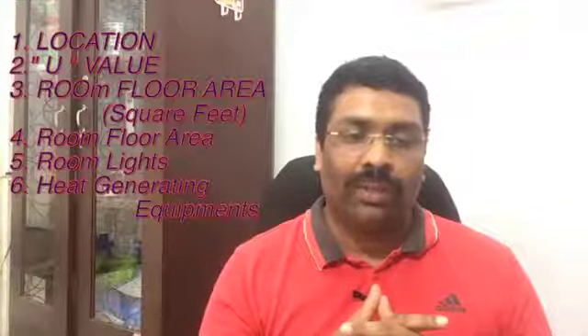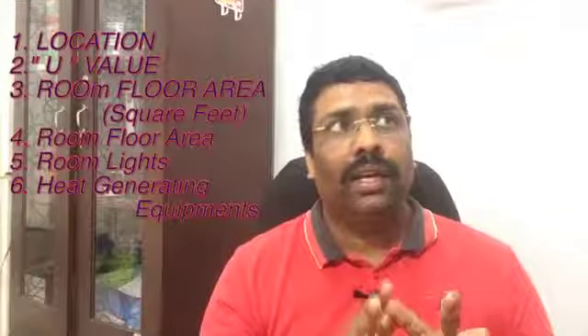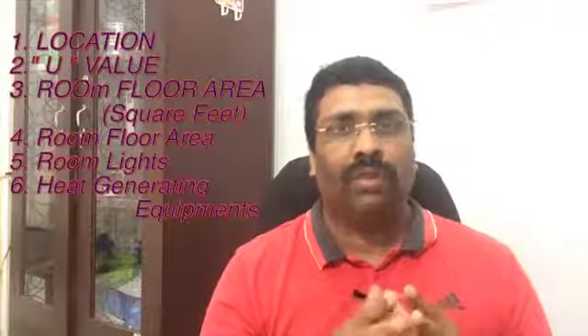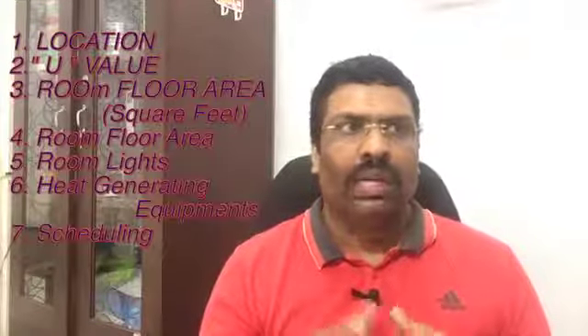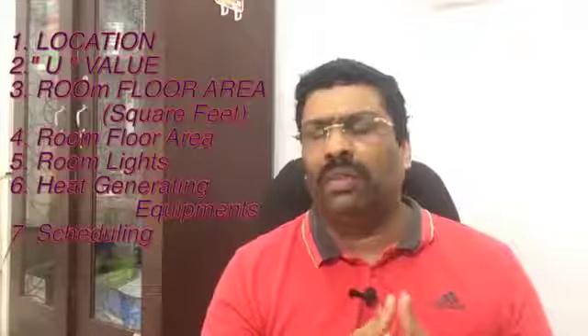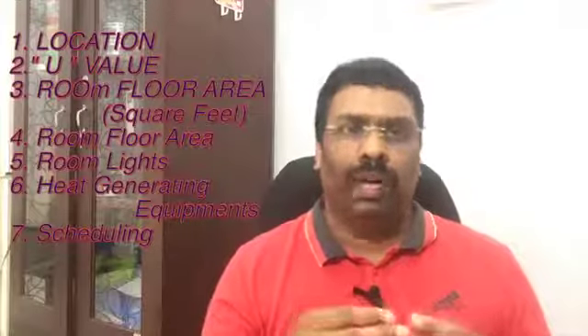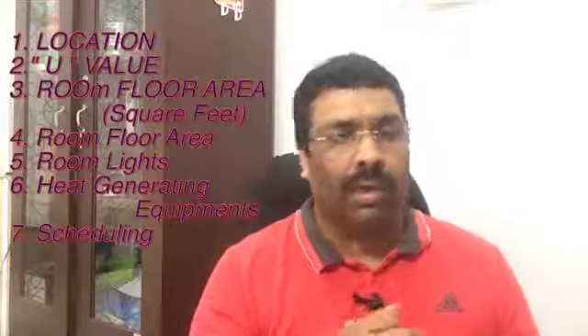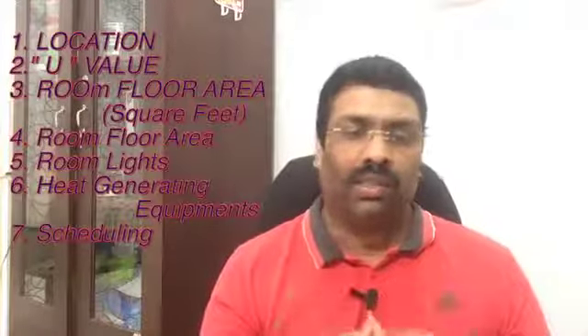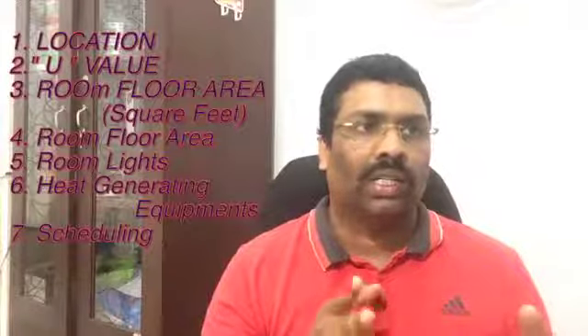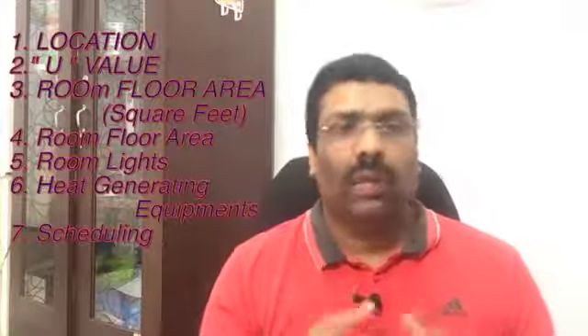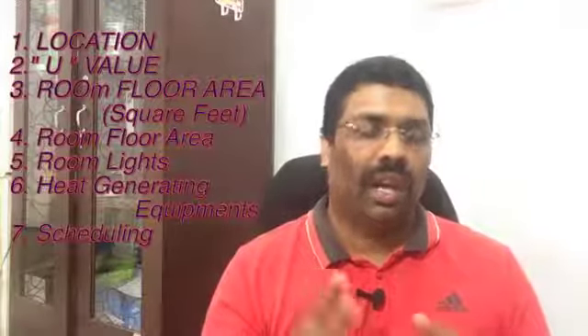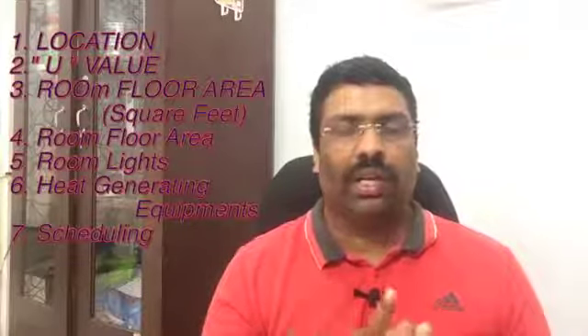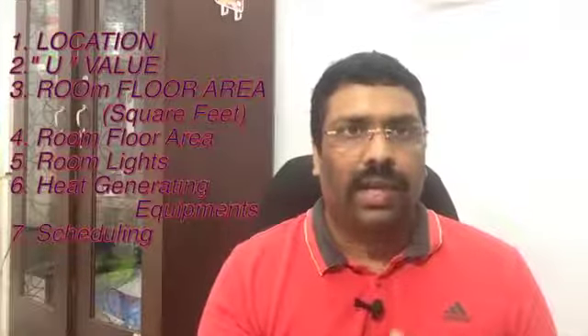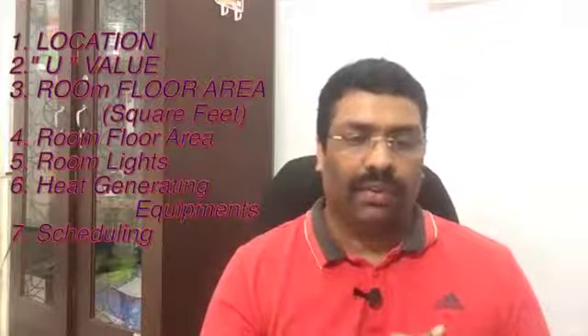The seventh point is there's an advantage in the HAP software: we can give intervals for lighting or equipment working hours. Normally in regular cases nobody does that, but for big commercial buildings we need to consider lighting and equipment intervals. Some equipment works only in daytime and is off at night, so the centralized AC system will automatically turn off or reduce speed at night. That's the interval we can set.